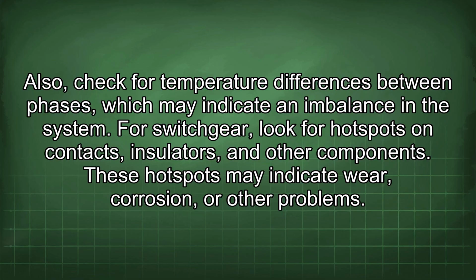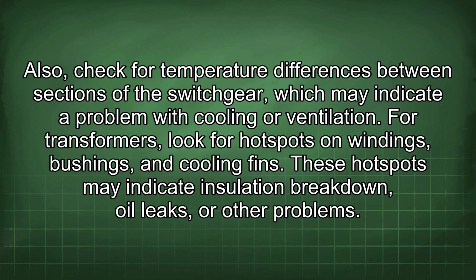For switchgear, look for hotspots on contacts, insulators, and other components. These hotspots may indicate wear, corrosion, or other problems. Also, check for temperature differences between sections of the switchgear, which may indicate a problem with cooling or ventilation.